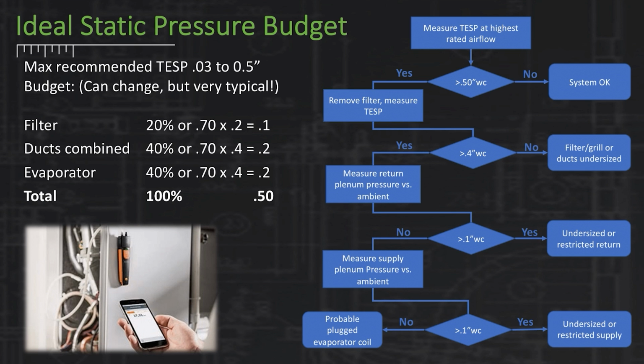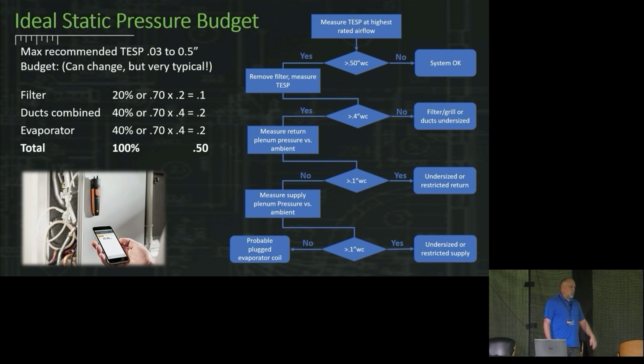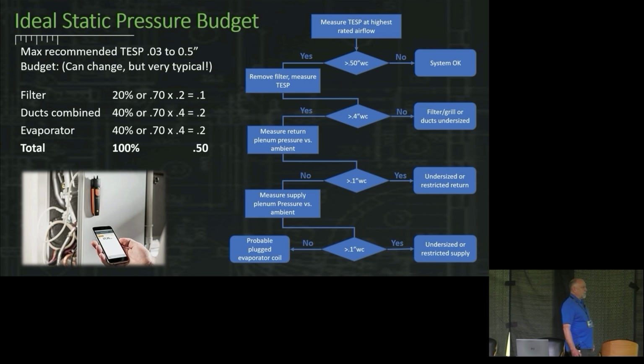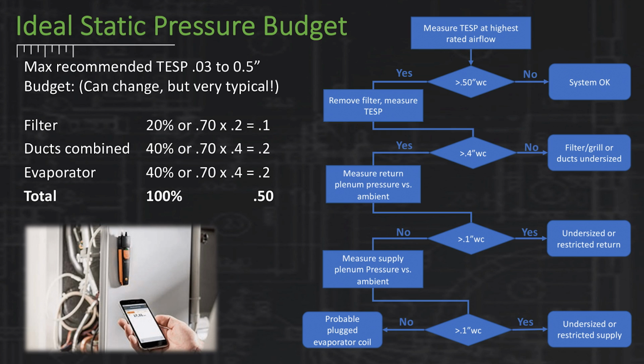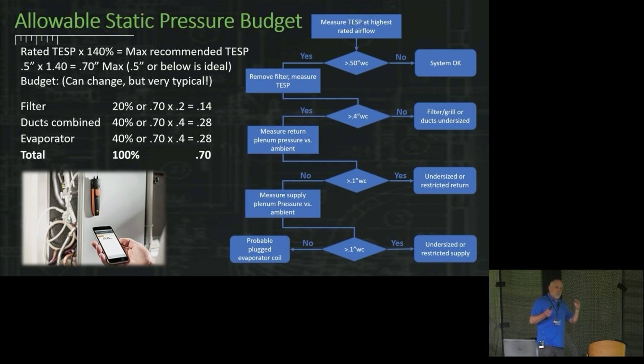Again, let me see if I can get ahead here. There's an ideal static pressure budget. NCI is wonderful about teaching you about static pressure budgets. Rob's been teaching that for years and years and years. But this is pretty standard in our industry. We do 1/10 of an inch for the filter, 2/10 for the ducts, 2/10 for the evaporator. That's your total, okay? And there's a little process flow chart here explaining the ideal budget. An allowable static pressure budget, you could be in the 0.14, 0.28, 0.28. But the idea here, this is a budget.